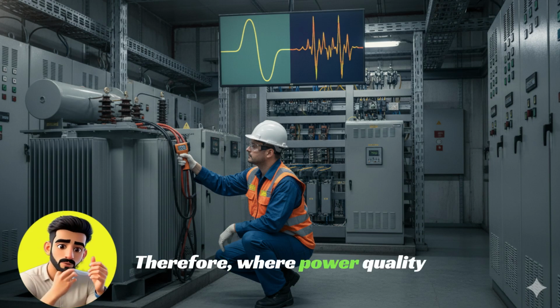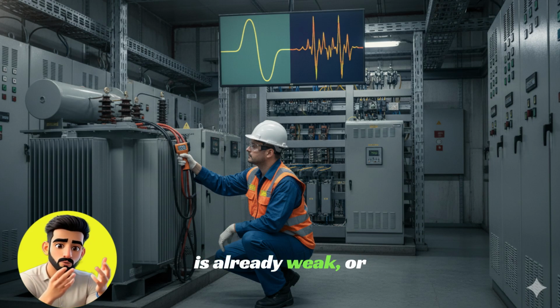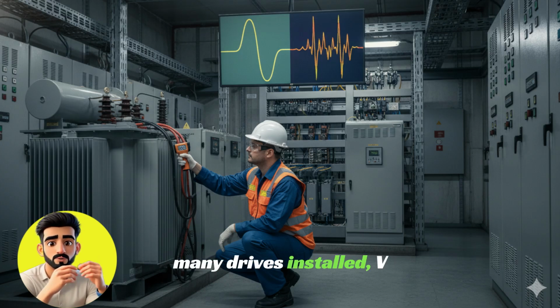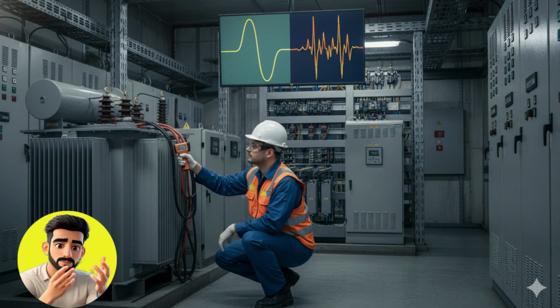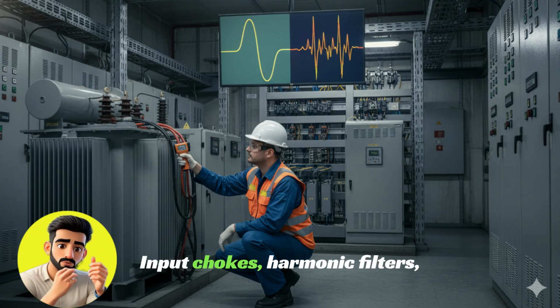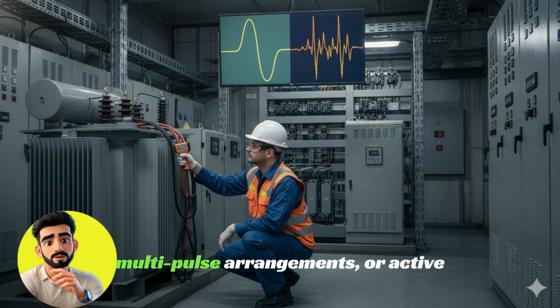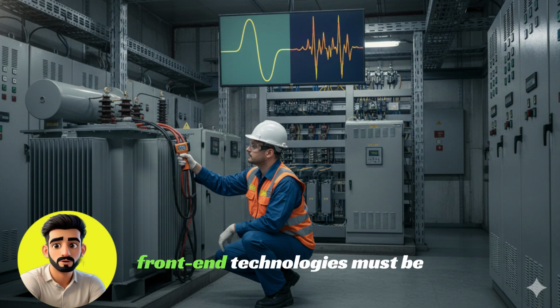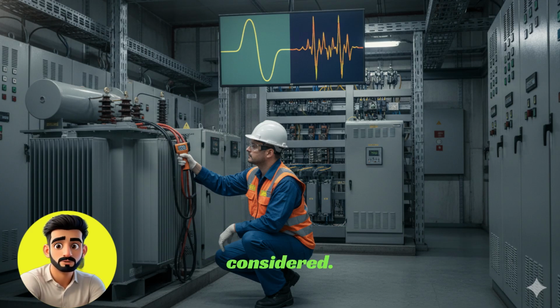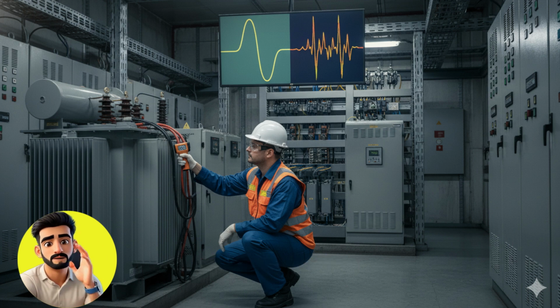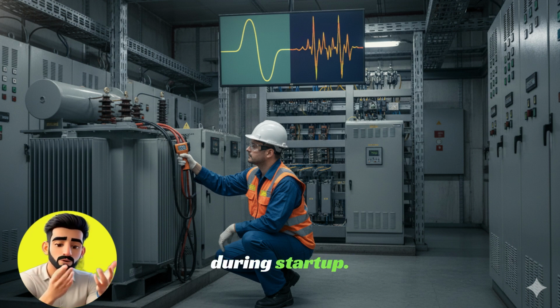Therefore, where power quality is already weak, or where the plant has many drives installed, VSD selection must be done carefully. Input chokes, harmonic filters, multi-pulse arrangements, or active front-end technologies must be considered. In this case, the soft starter is a cleaner neighbor. The impact is only during startup, and the duration is very short.